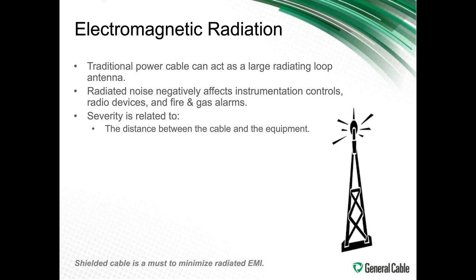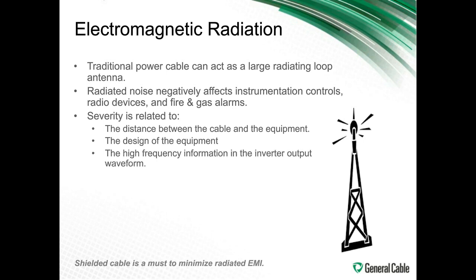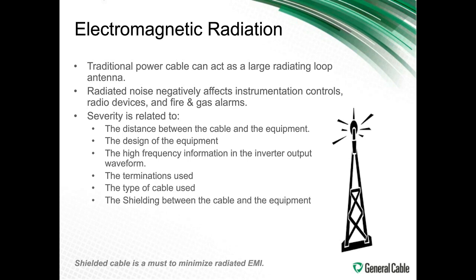Sometimes you don't have a lot of space there. And the design of the equipment is important. And of course, the high frequency information at the inverter output waveform is very critical to this. Also the terminations, to make sure you have a good grounded system on both ends. And the type of cable. The shielding between the cable and the equipment. All of these things contribute.